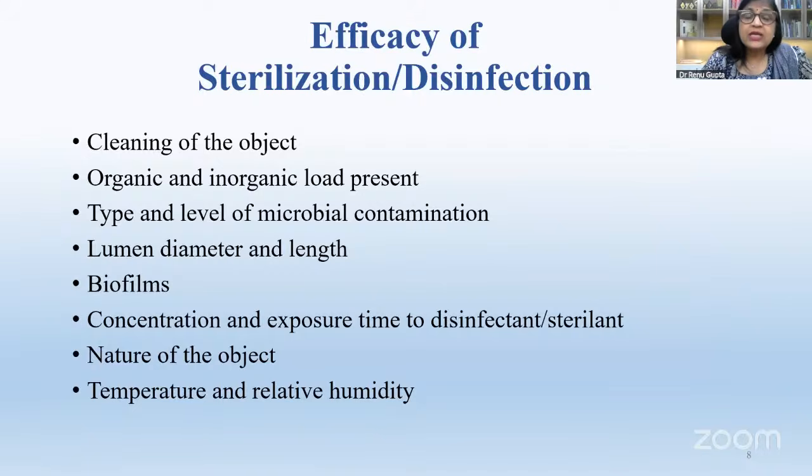Now, the efficacy of any sterilization or disinfection technique depends upon some factors. The most important factor is cleaning of the object. One take-home message from today's lecture is that cleaning is a prerequisite for any sterilization and disinfection. If you directly put any instrument into your autoclave, you will not achieve sterilization even if everything is working fine. The instrument has to be clean.